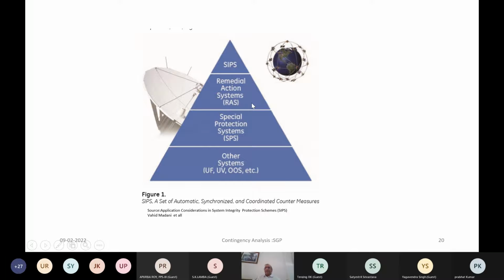These remedial action systems, again, there are a number of ways where you can create sufficient margin so that the risk of unstable operation can be minimized. And finally, the schemes are called system integrity protection schemes. In spite of all these levels 1, 2, 3, if we are not able to prevent certain abnormal conditions, then you need system integrity protection schemes.